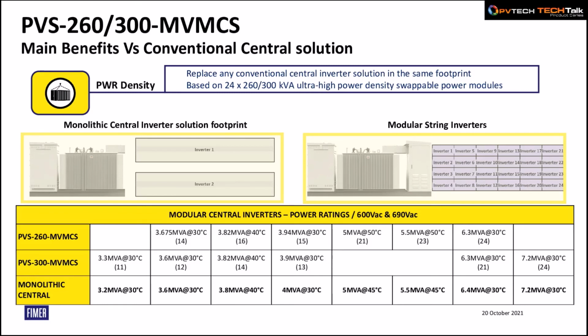So it will be important also to provide a solution for these systems. With the same footprint of a conventional monolithic central inverter, we can provide one-to-one replacement for building blocks of 3 megawatt, 3.2 megawatt, as well as the largest capacities available today for monolithic inverters, exceeding 7 megawatt.